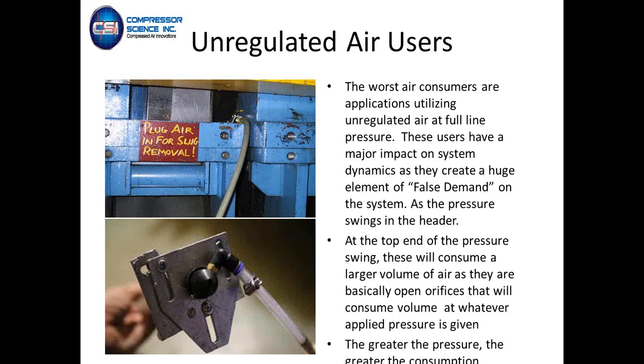A lot of times we're going to see the flow going up and down, and then we're going to see the pressure in the compressed air header swinging up and down. In some cases, we see swings of 25 to 30 psi. And what happens at the top end of the swing, if you're getting up to your 100 psi, then all those leaks and all those unregulated users are going to consume at that orifice chart rate at 100 psi, that larger volume of air.